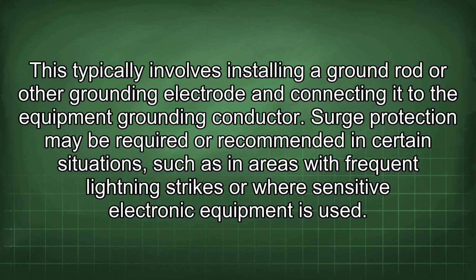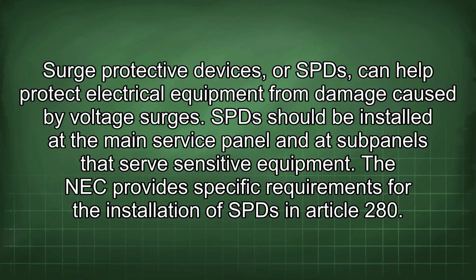Surge protection may be required or recommended in certain situations, such as in areas with frequent lightning strikes or where sensitive electronic equipment is used. Surge protective devices, or SPDs, can help protect electrical equipment from damage caused by voltage surges. SPDs should be installed at the main service panel and at subpanels that serve sensitive equipment. The NEC provides specific requirements for the installation of SPDs in Article 280.